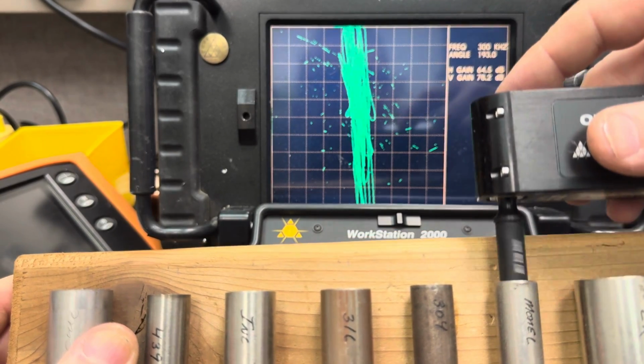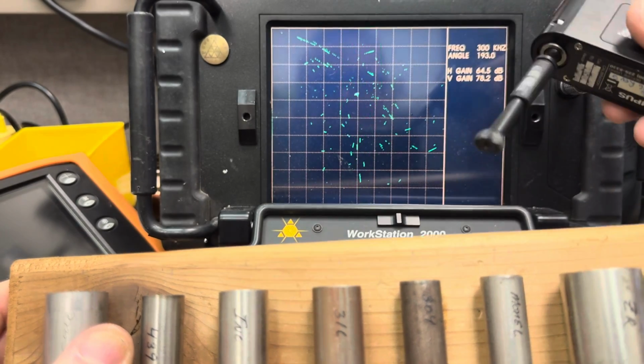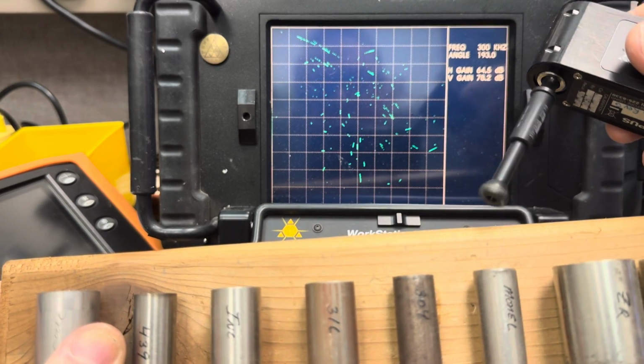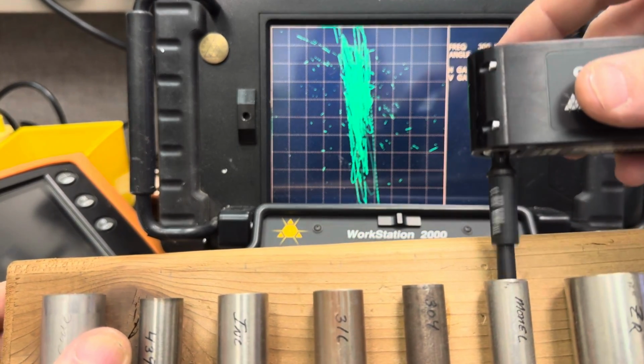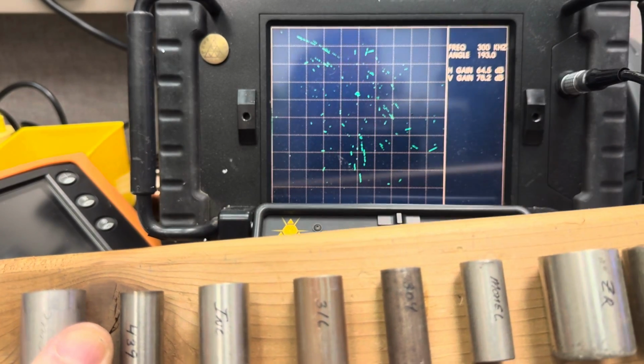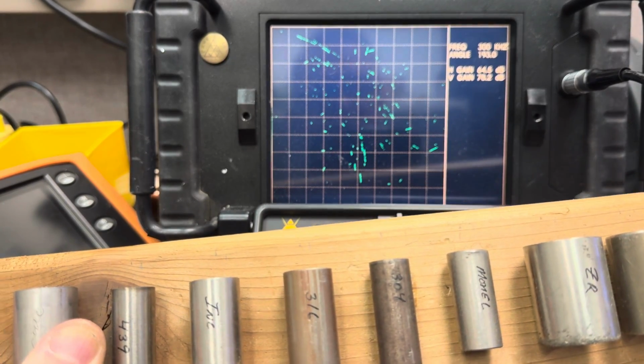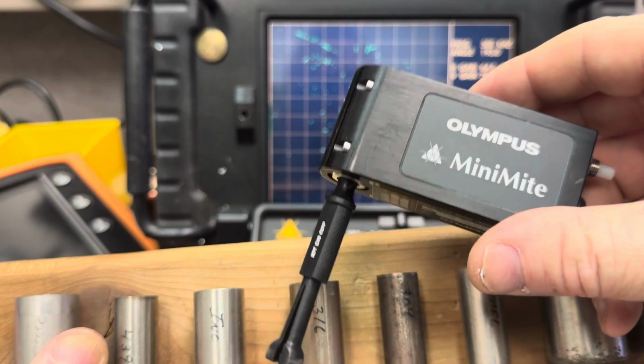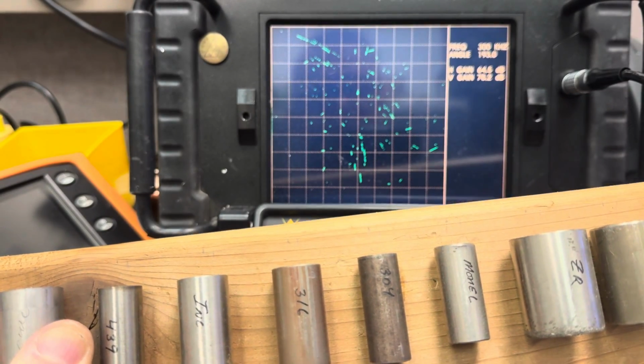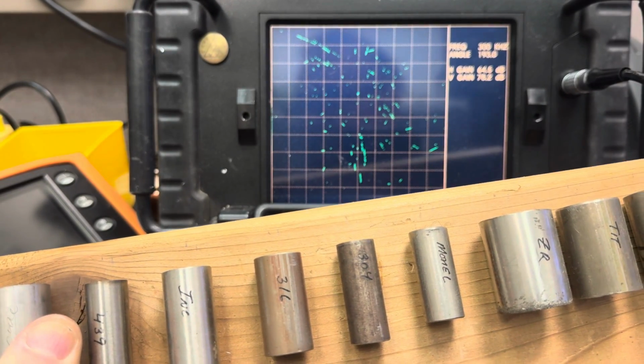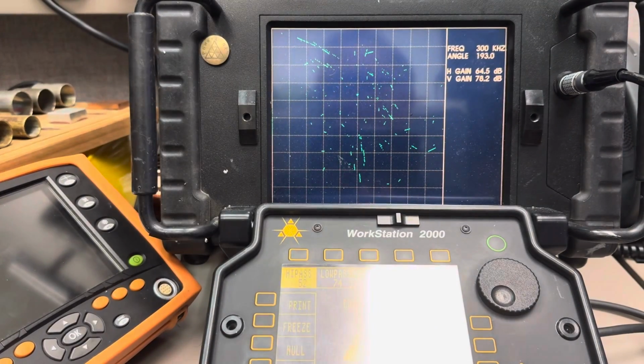That's just an example of how you can use rotating coils to examine tubes, because they're really just like big fastener holes, right? But you can't use this scanner in an installed heat exchanger, especially if it's in a radiological environment, because you'd be soaking up too much dose, so that's not good. So how do you do it?